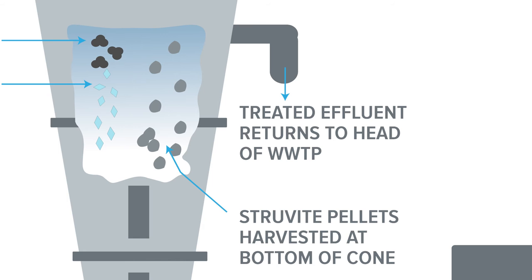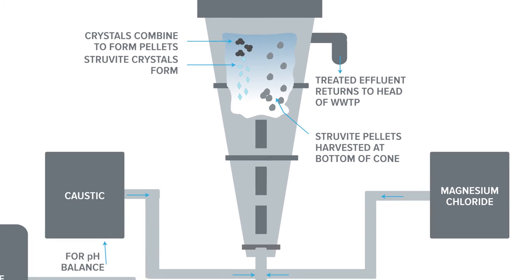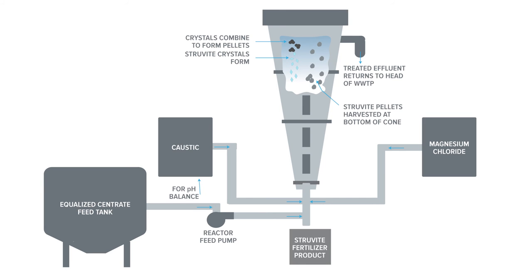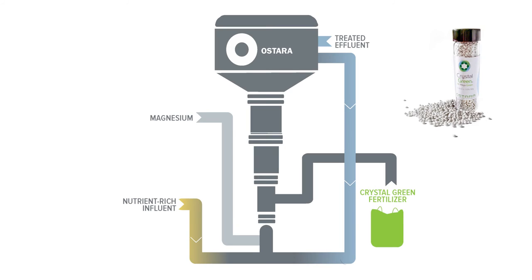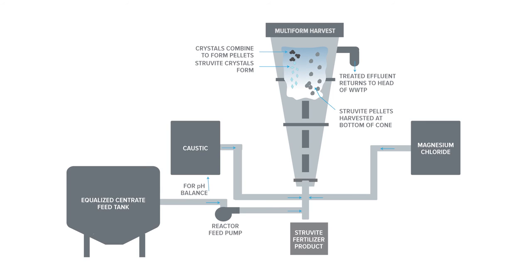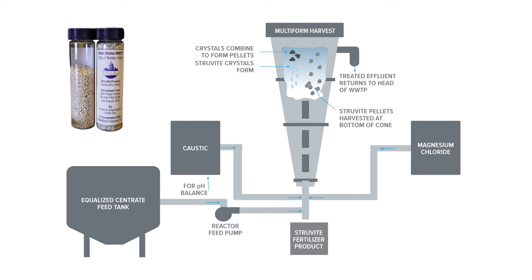The low-phosphorus effluent exits the top of the reactor, and the phosphorus, as struvite, comes out the bottom. Depending on the manufacturer, an internal recycle might be required. The resulting pellets from the Ostara process are ready to sell — they call it Crystal Green fertilizer. From Multiform Harvest, the finished product is a raw form of struvite with a sandy consistency, which gets processed into fertilizer or other products off-site on the secondary market.